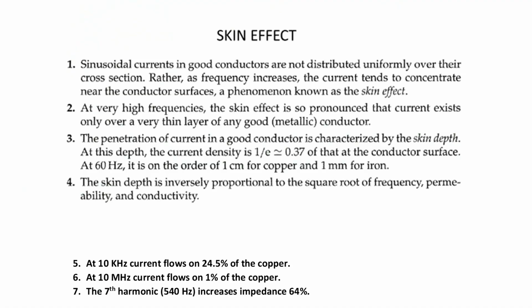So basically what it's saying is the amount of copper at 10 kilohertz uses like 24% of the copper. The higher the frequency, pretty soon you're only using 1% of the copper. So I just got to provide more copper. And I can't do that with building wire because it only comes with either 7 or 19 strands.